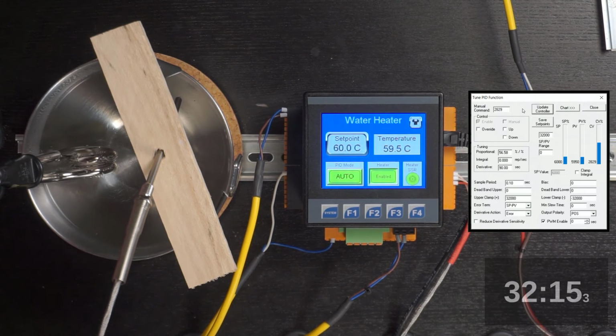It doesn't appear to be helping. If anything, it probably appears to be taking it the other direction. So I'm going to let it go up through this cycle, and then I'm going to try reducing it by half. So it was at 45 originally. I doubled it to 90. Next, I'll try dropping that down to, let's say, 20 to see if that offers an improvement or not. But I'll wait a couple minutes before I do that.